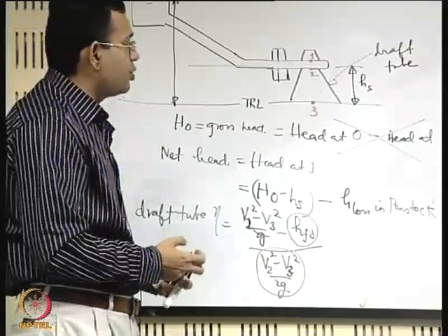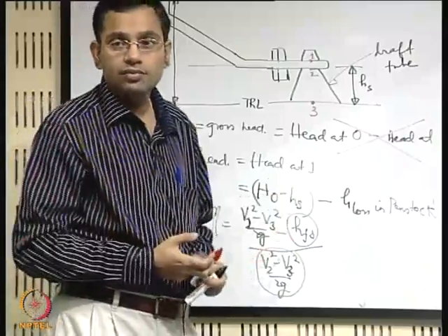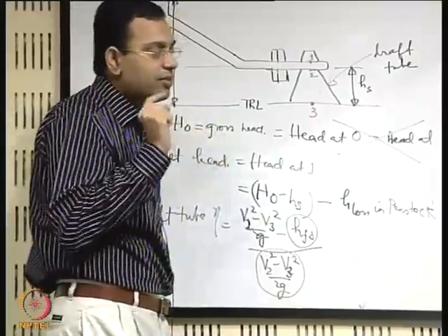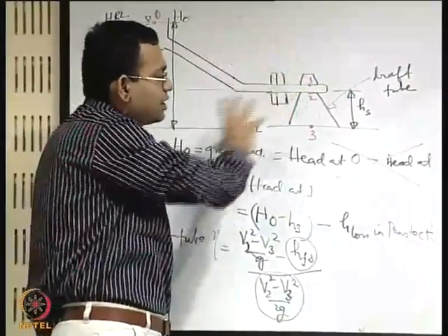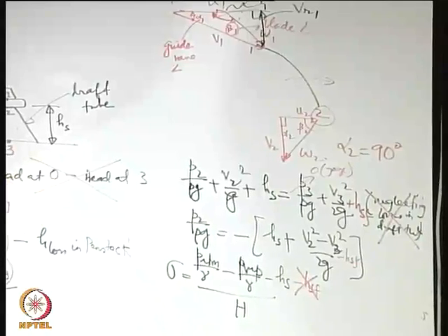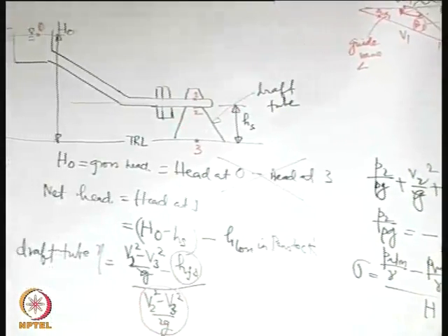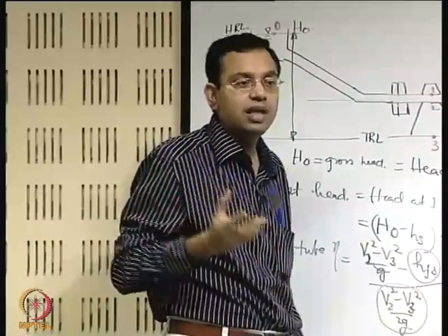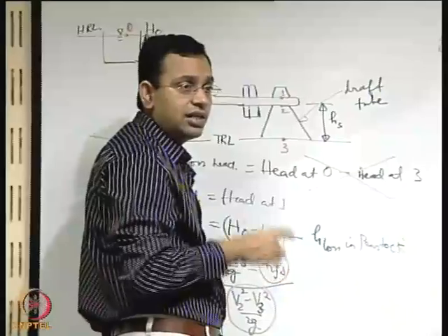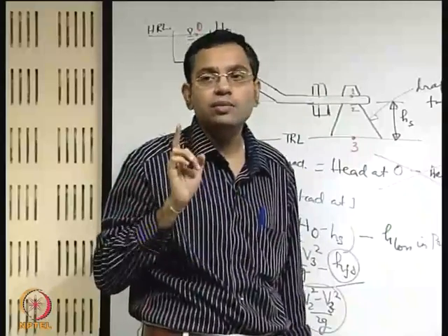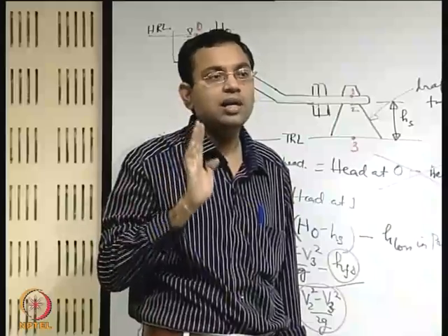The big question is, when you have a draft tube, do you have a draft tube for an impulse turbine? Say, would you have a draft tube for a Pelton turbine? One of the important objectives that the draft tube fulfills is that in the reaction turbine, you can see that there is a partitioning between the pressure change and the velocity change, and that is important. In an impulse turbine, that is no more important, because everywhere you have the pressure as the same. There is no change in pressure as the fluid is passing through the turbine, and therefore you do not require something like a draft tube. So the draft tube also affects the change in pressure. That is one of the very important things, and that is an integral part of the turbine. By basic principle of an impulse turbine, you should not have a change in pressure across that. Then it is no more an impulse turbine. Therefore, an impulse turbine will never have a draft tube.